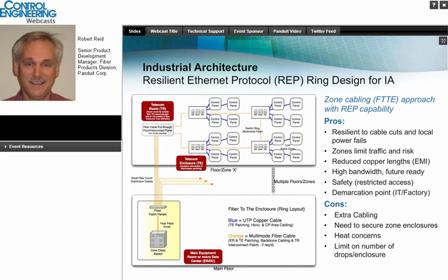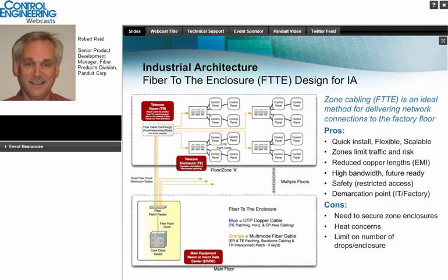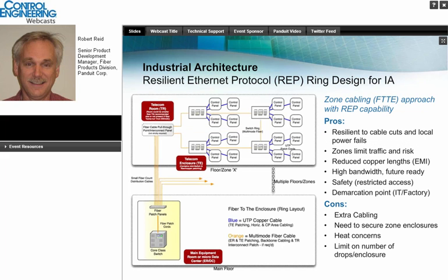We can take the same approach, this TE approach, into ring design. So what I've done here, and I'll toggle back and forth between these two slides, is I've got the same zone approach where I'm zoning the cabling into these little enclosures. But now, instead of starring out to these enclosures, these TEs, I've kind of closed the loop. So I actually have a ring network.